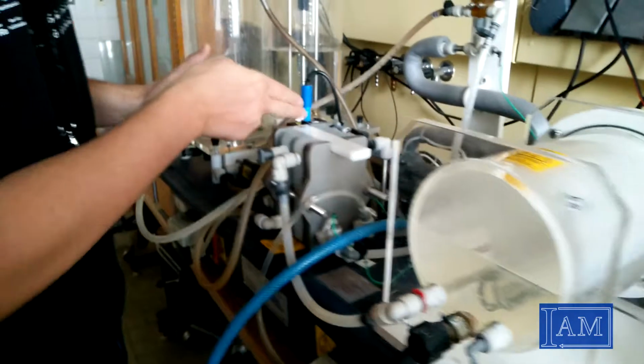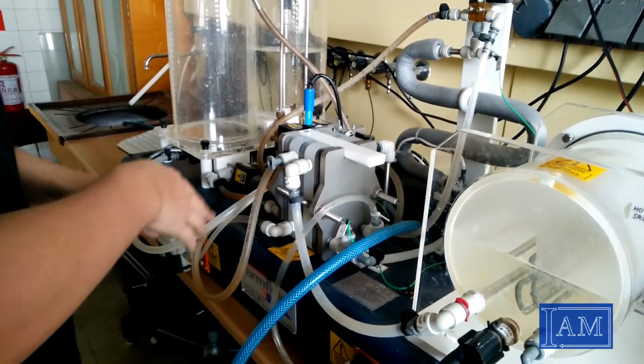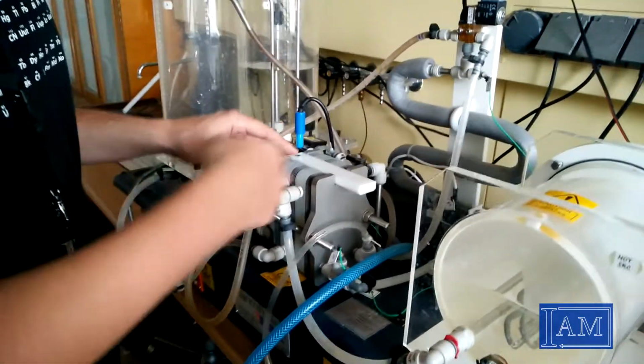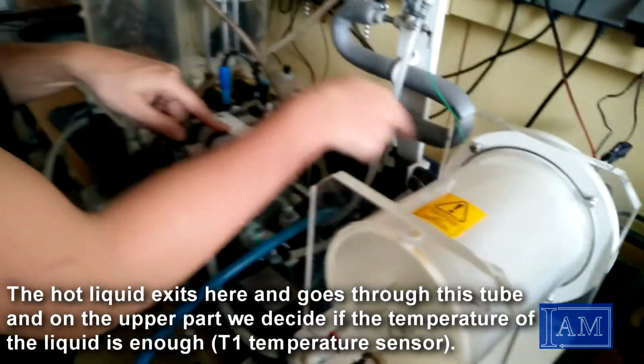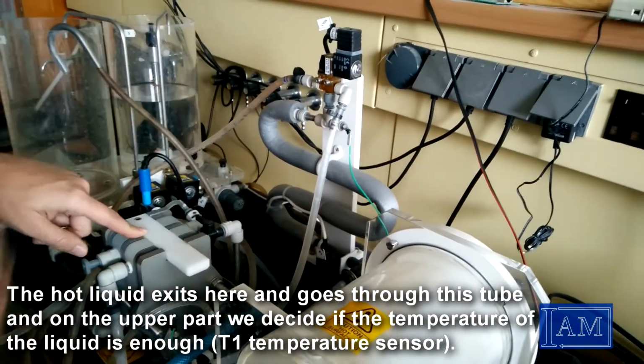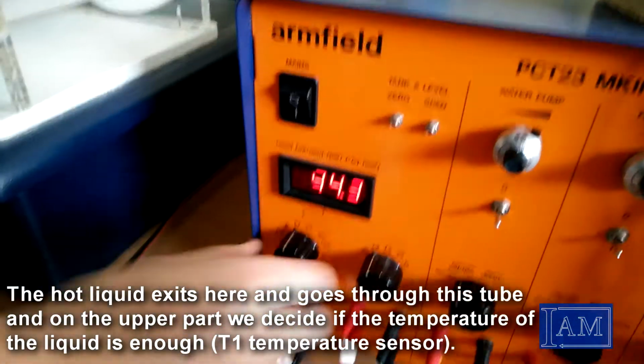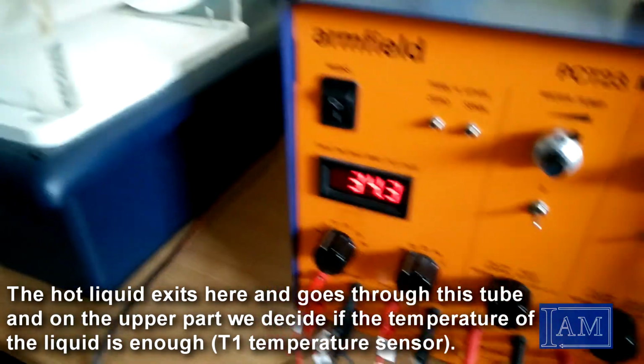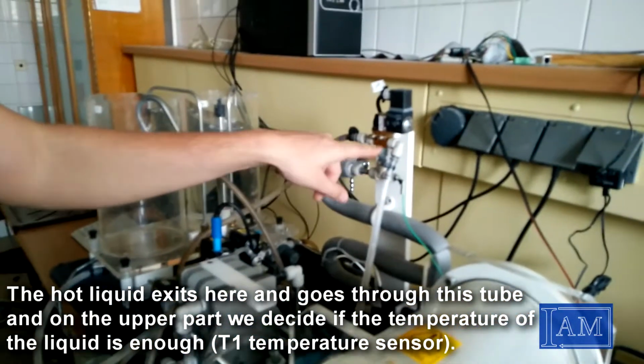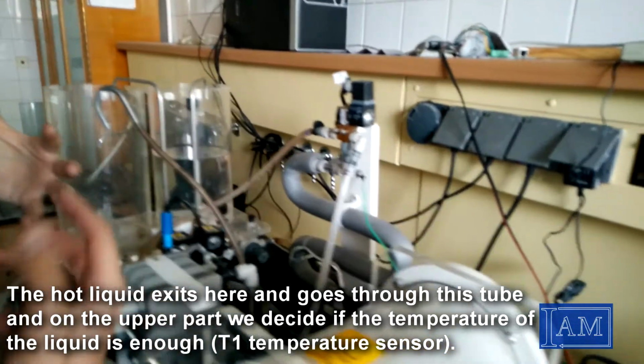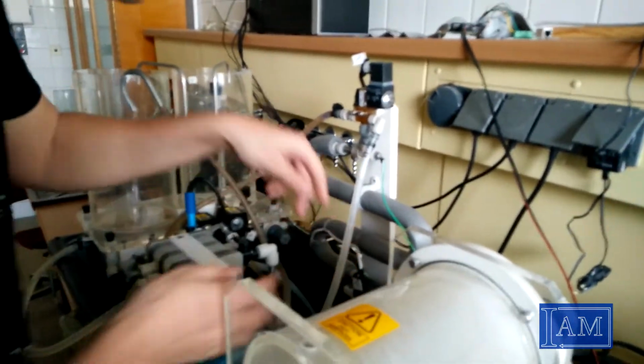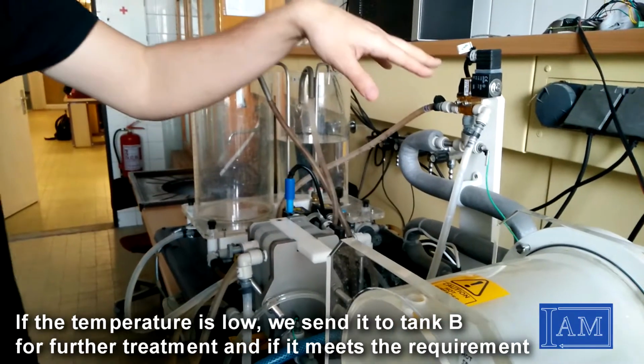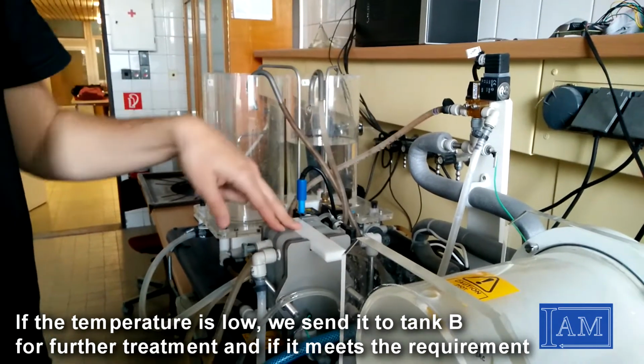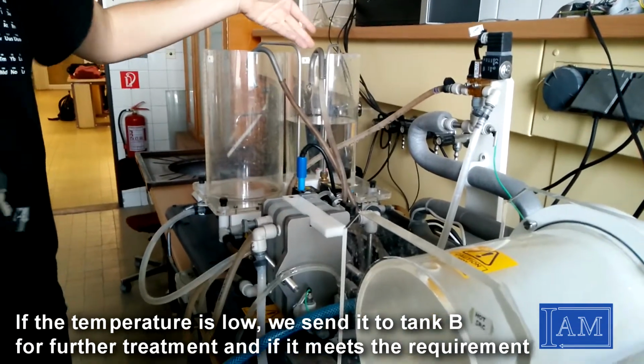The water exits the heat exchanger, it goes through this tube, and on the upper part we decide if the temperature of the liquid is enough. This measures the T1 temperature sensor, and while the temperature doesn't meet the requirements, we will send the liquid back to the tank for further treatment.